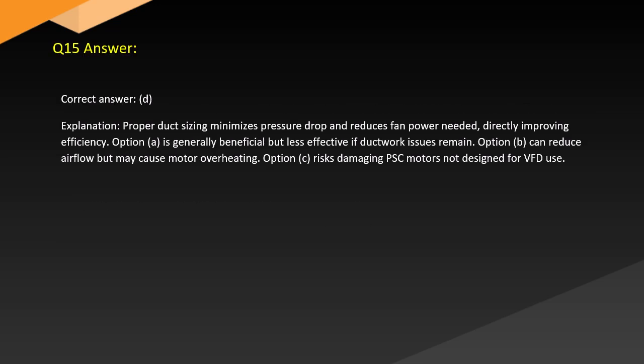Answer. Correct answer, D. Explanation. Proper duct sizing minimizes pressure drop and reduces fan power needed, directly improving efficiency. Option A is generally beneficial but less effective if ductwork issues remain. Option B can reduce airflow but may cause motor overheating. Option C risks damaging PSC motors not designed for VFD.